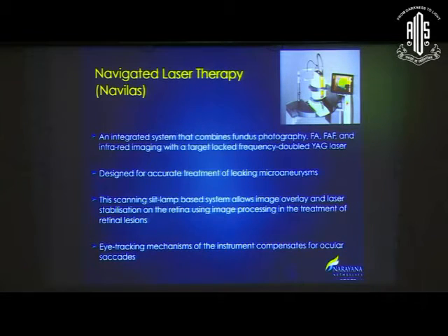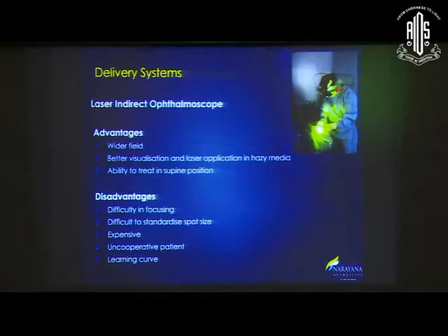So here basically the target is locked. It's designed for accurate treatment of leaking microaneurysms. This scanning slit lamp based system allows image overlay and laser stabilization on the retina using image processing in the treatment of retinal lesions. Eye tracking mechanisms also exist in the system, and this compensates for the ocular saccades.